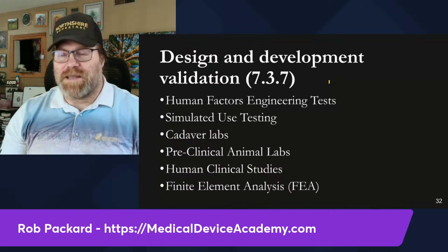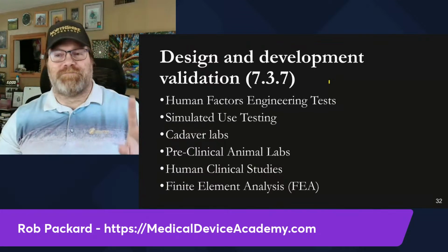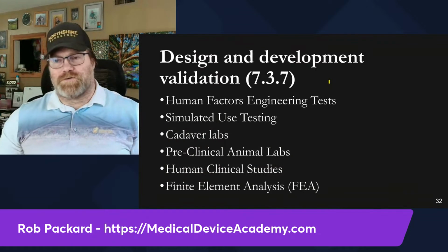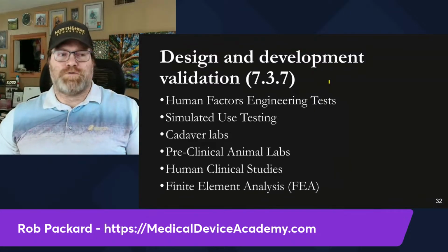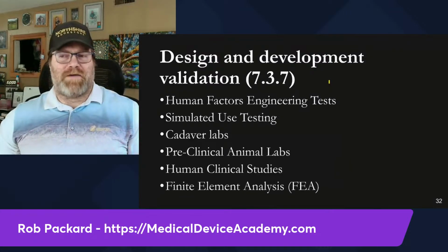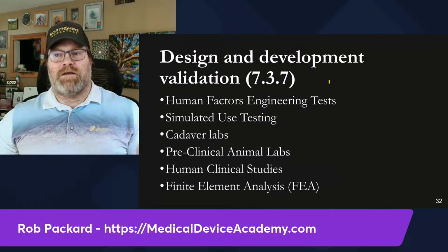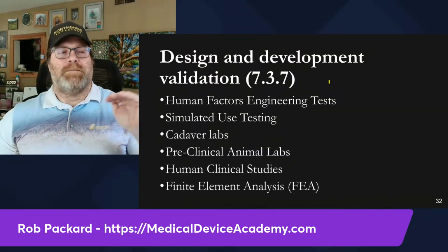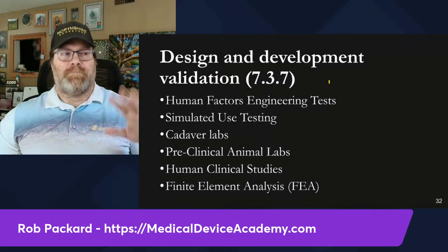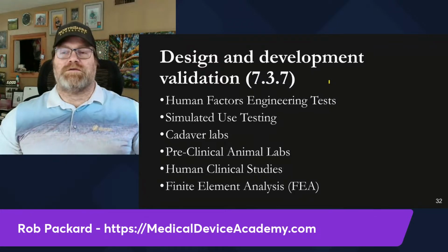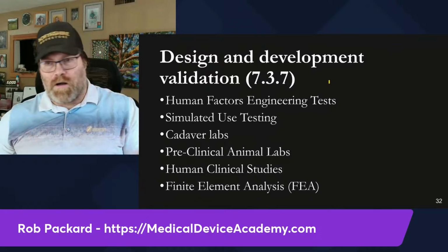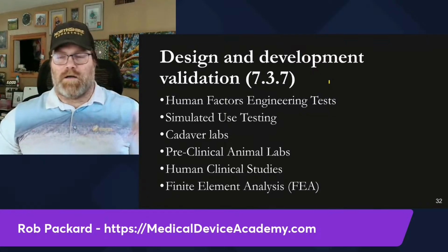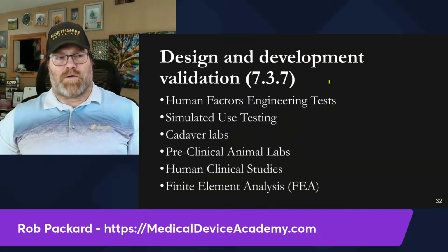Then we have validation. In this case, because verification and validation are so similar in terms of wording, I just put in here what the typical validation tests are that are seen for medical devices. Human factors engineering is at the top of the list because that's what we're seeing the most. People are surprised by it because it wasn't enforced in the past. Now all the Europeans are requiring and all the FDA reviews are requiring it.